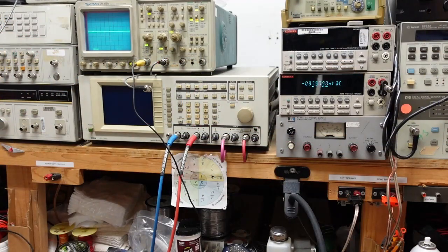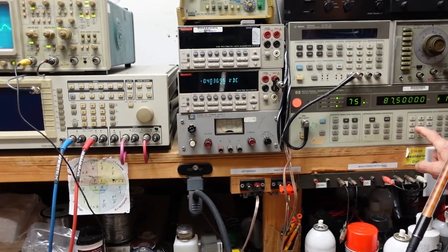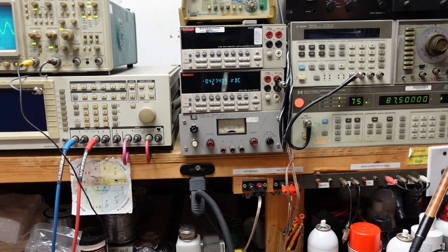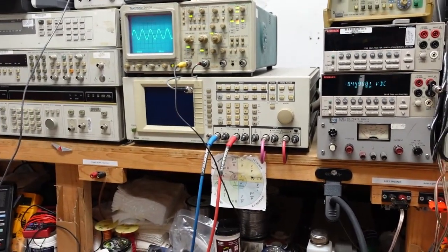Okay, so the next thing they're going to want from us is they want the distortion touched up. So for that we need to turn our modulation back on and we need a good strong signal. And the manuals usually recommend 1 kilo microvolt, which in the real world is known as 1 millivolt. 1000 microvolts, 1 millivolt. So we set the amplitude on the generator for 1 millivolt. You see we have a really nice solid sine wave.